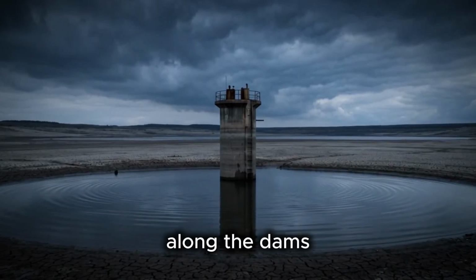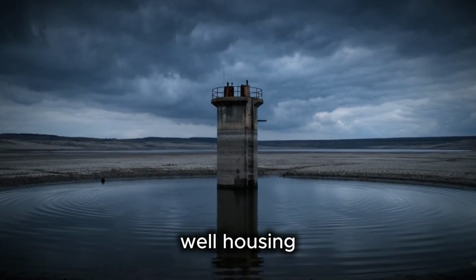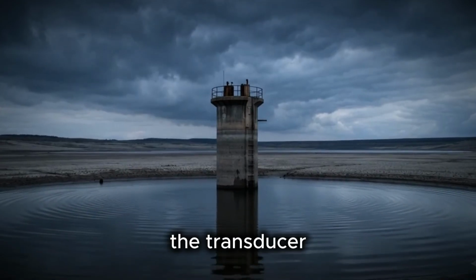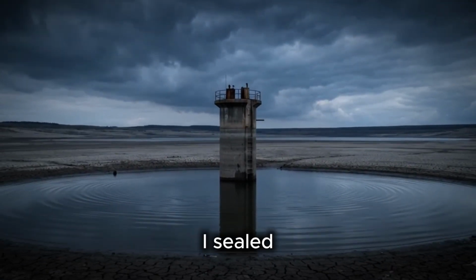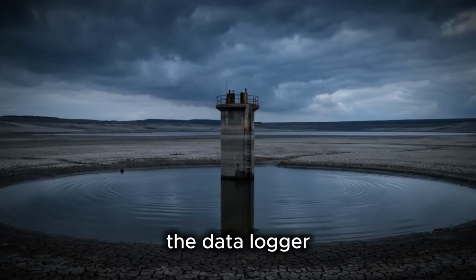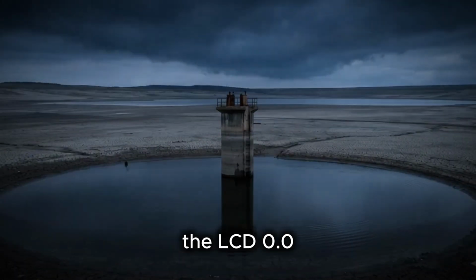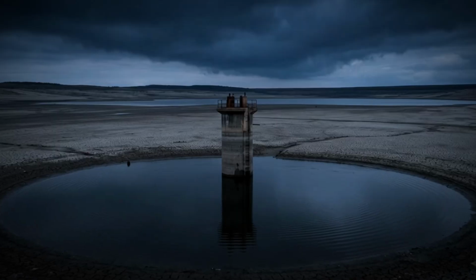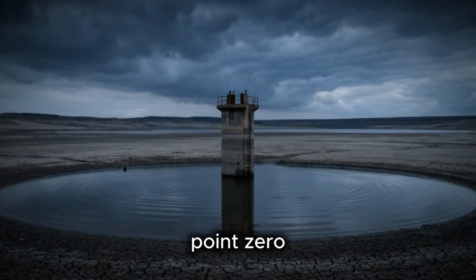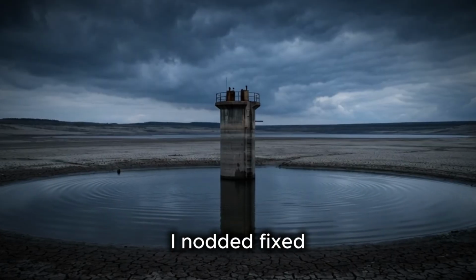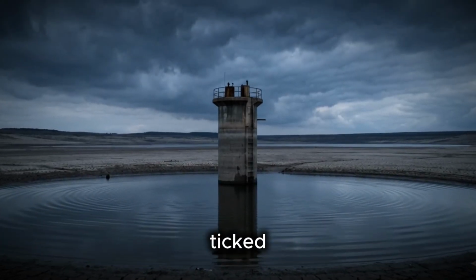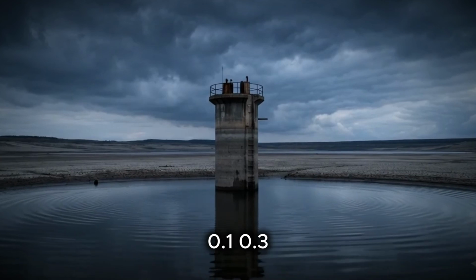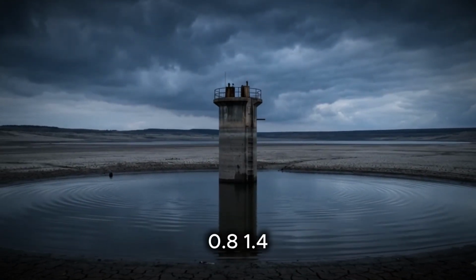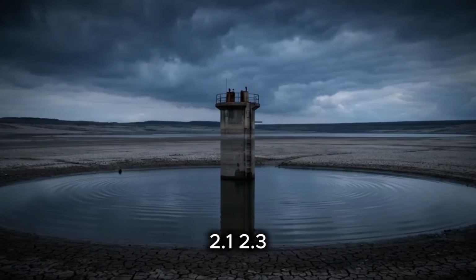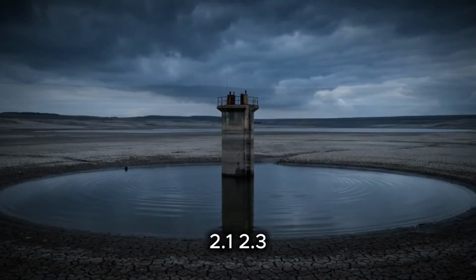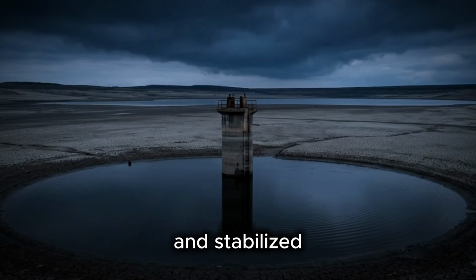I walked out along the dam's maintenance catwalk to the stilling well housing and replaced the transducer. 20 minutes. I sealed the housing, powered up the data logger, and watched the LCD: 0.0, 0.0, 0.0. I nodded, fixed. Then the display ticked: 0.1, 0.3, 0.8, 1.4, 2.1, 2.3. It climbed in about 90 seconds and stabilized.